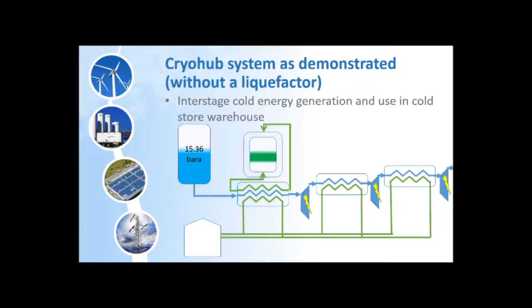As you may imagine, the volume of these heat exchangers would increase with lower and lower inlet pressure from the cold gaseous nitrogen, and therefore on the third stage of expansion the pressure will be about ambient, meaning that we will need a much larger volume heat exchanger to transfer pretty much the same amount of heat as the interstage heat exchangers. So this will prove uneconomical, and therefore we decided to drop the heat exchanger. So let's go to the crunching numbers.